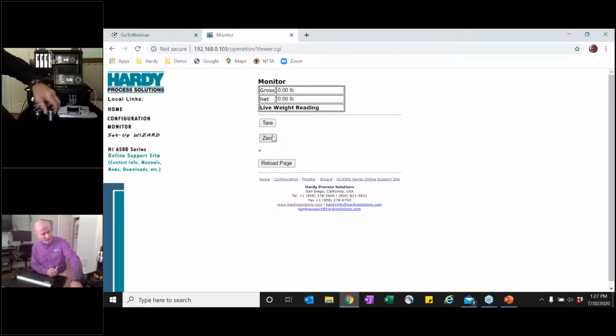So what we'll do now is on the front panel of the unit, I'm going to go in and we're going to take this out of calibration. So we've got a wizard here, an up or down wizard, and we just use the up or down buttons to pick the one we want. We want calibration, it's on calibration. So we'll go ahead and calibrate it. Now, we can do the smart calibration as the C2 calibration, but in this case, we don't want to do that. We want to do a hard calibration because we want to mess this scale up. So we'll enter the hard calibration.